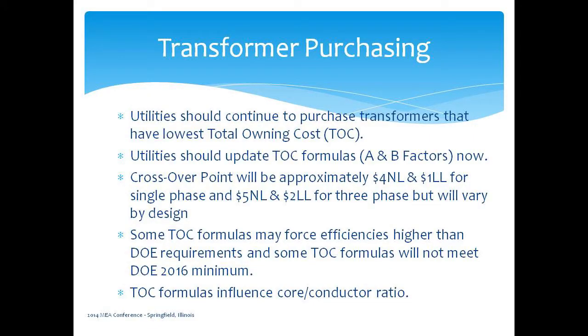One good example of this, and you're going to see it here recently in 2010 DOE: the current method of operation, when you look at about $3 and $1 on a three-phase pad, then you start seeing the possible need to maybe consider amorphous. Now you're going to see that crossover point shift. It's going to go up a little higher. From what we can see, it's going to be about $4 and $1 for the single phase, and over $5, $5 and $1, for three phase. So you'll see that little bit of a shift between the single phase and the three phase between your A and B factors.